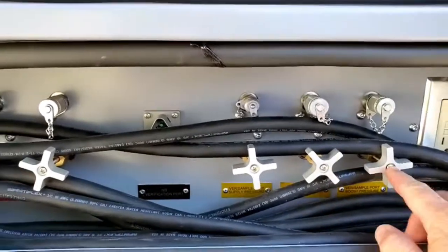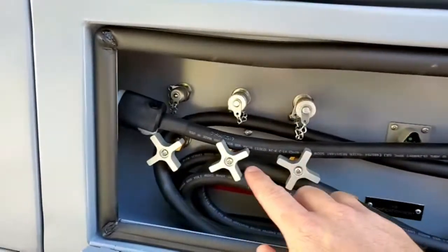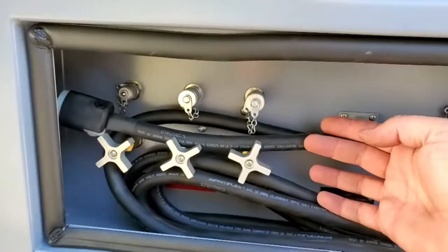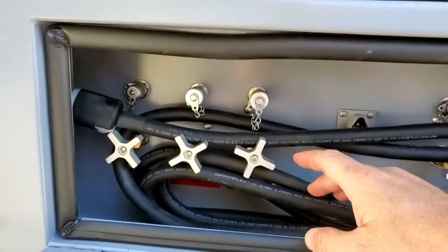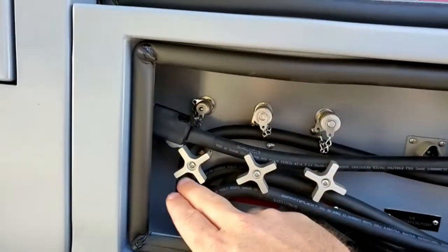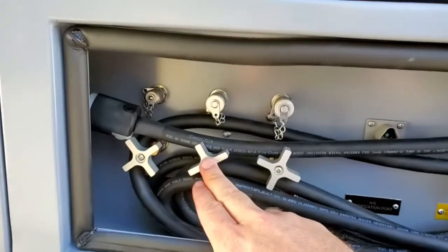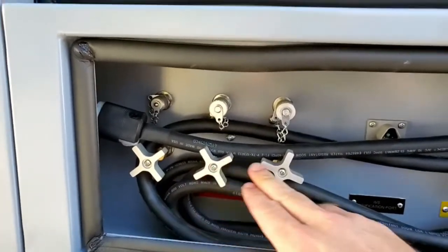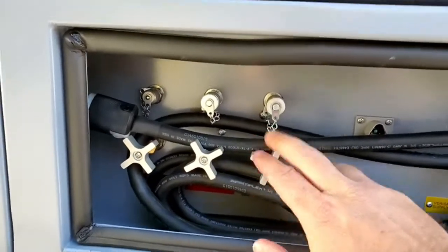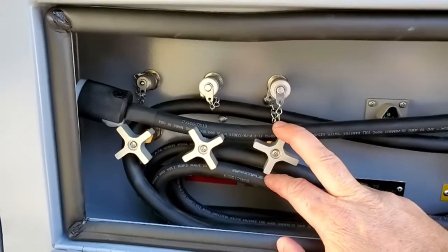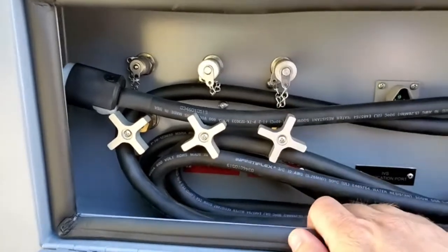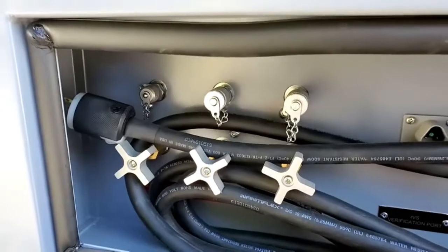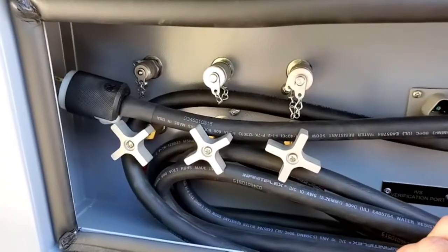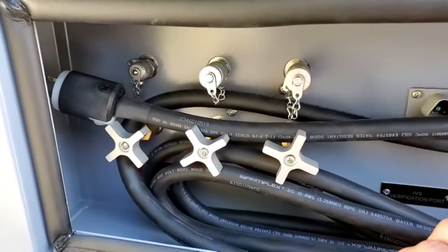Now the purpose for ensuring that each of these is fully counterclockwise is that behind this panel are the pressure transducers. So here you have supply pressure, boost, return pressure, and boost pressure. If this is closed, your pressure transducer will not receive the pressure that it needs in order to indicate. You can encounter various false positive faults.